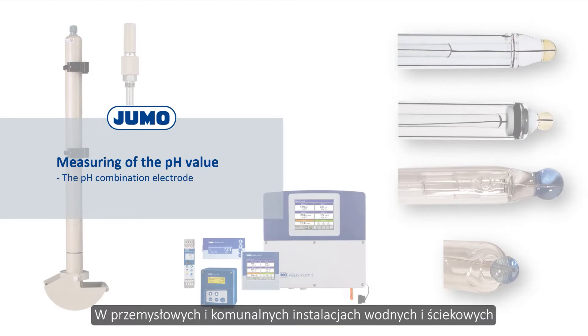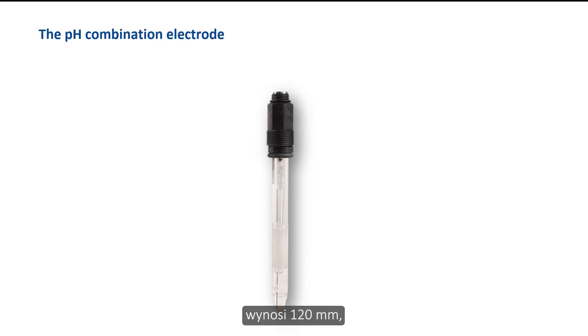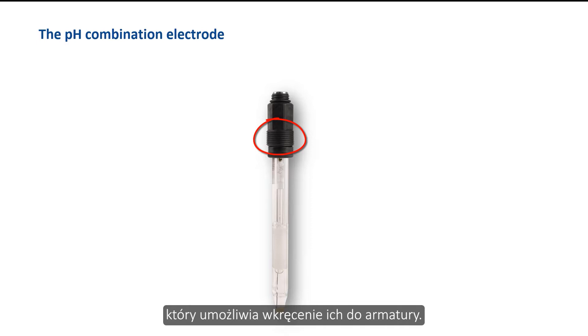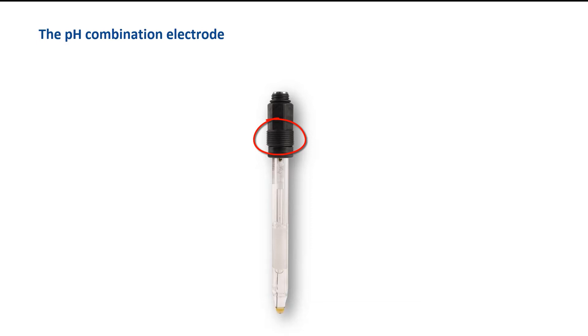In industrial and municipal water and wastewater plants, combination electrodes are generally used for online measurements. The standard installation length of the combination electrodes is 120 mm, and the electrodes usually have a PG13.5 external thread which allows them to be screwed into a fitting. The electrodes have two chambers which house the measuring and reference systems.